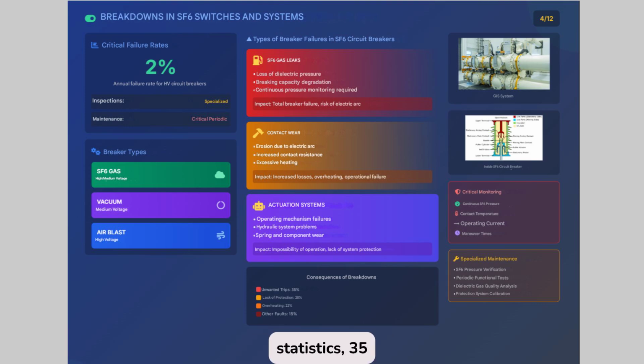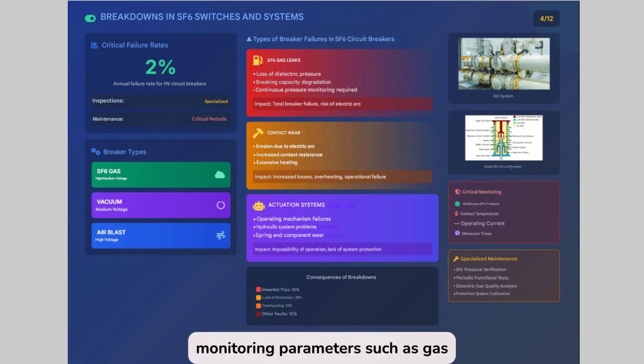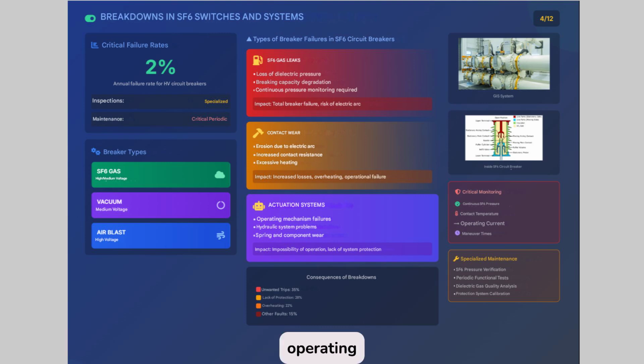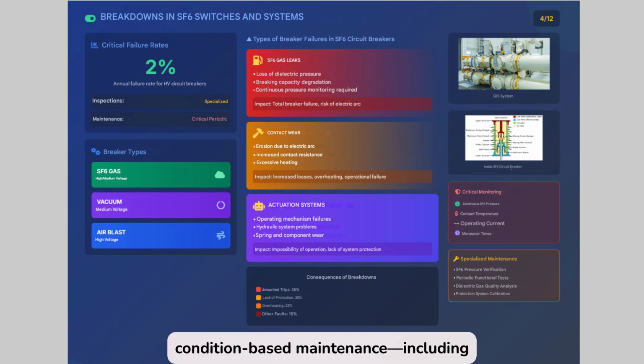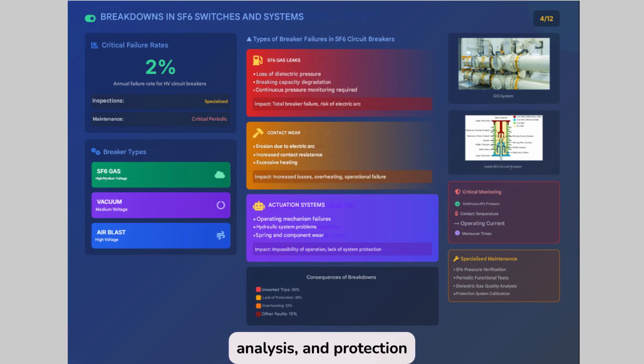According to statistics, 35% of faults cause unwanted tripping, 28% involve loss of protection, 22% cause overheating, and 15% correspond to other problems. These data underscore the need to detect breaker degradation early by monitoring parameters such as gas pressure, contact temperature, current, and operating times. Implementing specialized condition-based maintenance, including functional testing, gas analysis, and protection calibration, not only prevents failures, but also extends the equipment's lifespan. A breaker failure is not a minor incident. It can trigger a chain of consequences. Therefore, anticipating this with appropriate sensors and robust maintenance protocols is not only a technical measure, but also a smart financial strategy in an increasingly demanding sector.